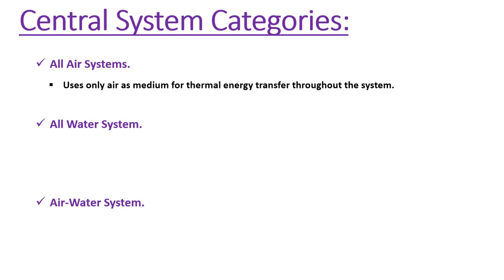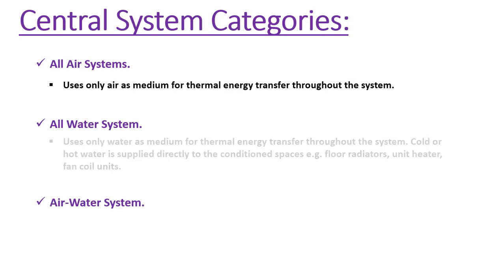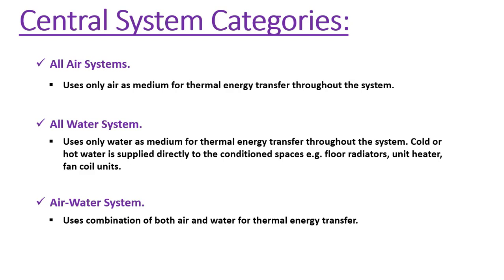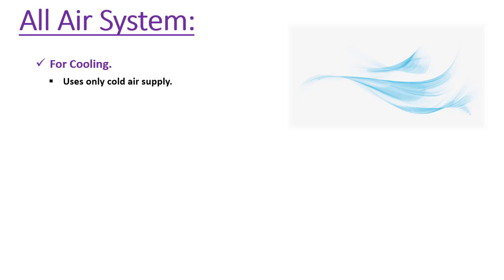All air systems use only air as the medium for thermal energy transfer throughout the system, while all water systems use only water as the medium. Cold or hot water is supplied directly to the conditioned spaces; examples include floor radiators, unit heaters, and fan coil units. Air-water systems use a combination of both air and water for thermal energy transfer.